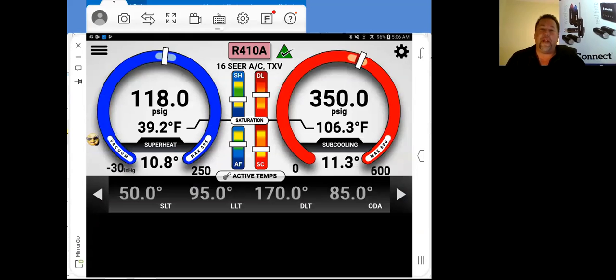What I'm going to do right now is simulate a small issue so we can do a bit of a differential between a measurement in and a measurement out. When you're going into a project and taking a measurement in and a measurement out, the measurement in is basically the way the system was when you approached it - whether it's running inefficiently, needs a lot of adjustment, or it's a first-time commissioning where there needs to be a refrigerant adjustment because of the length of the line set. You can take a measurement in and a measurement out.